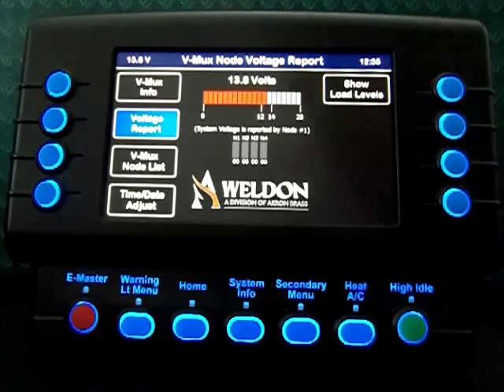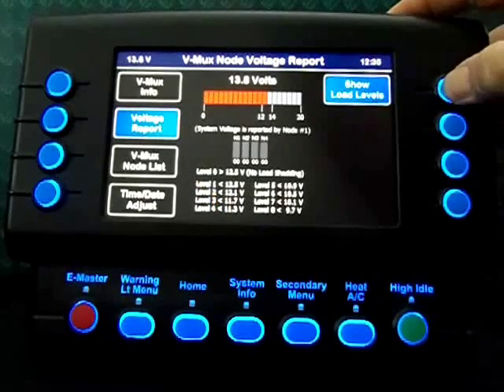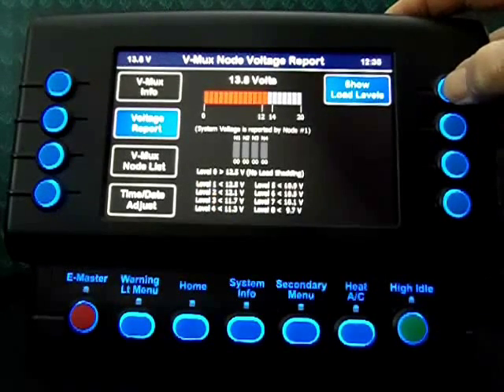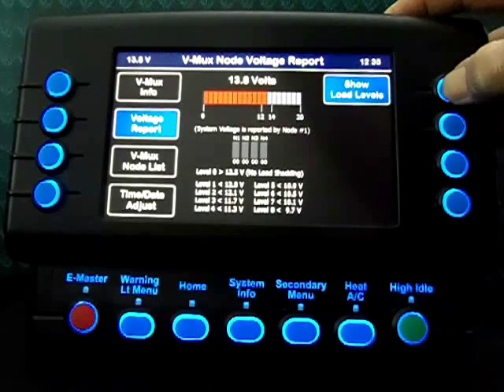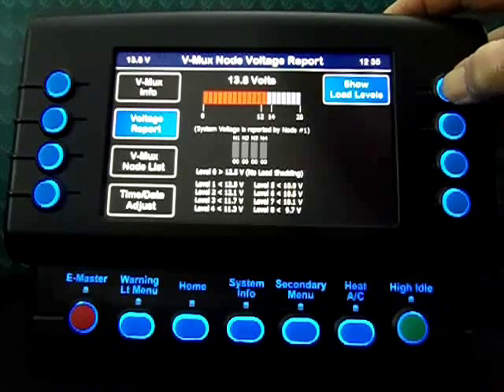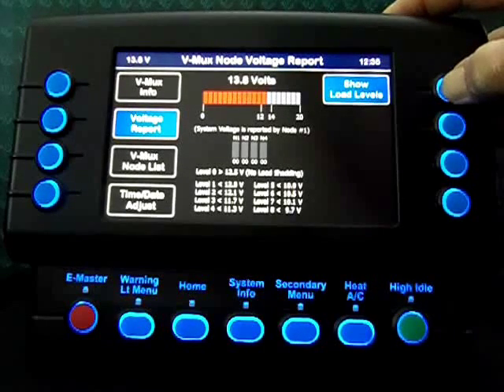I have a graphical representation of load shed levels. Right now, all nodes are at level 0. With level 0, we're above 12.5 volts. At level 1, we would be below 12.5. Level 2 is below 12.1 volts. Level 3 is below 11.7. Level 4 is below 11.3. Level 5 is below 10.9. Level 6 is below 10.5. Level 7 is 10.1 volts. And finally, level 8 would be below 9.7 volts.